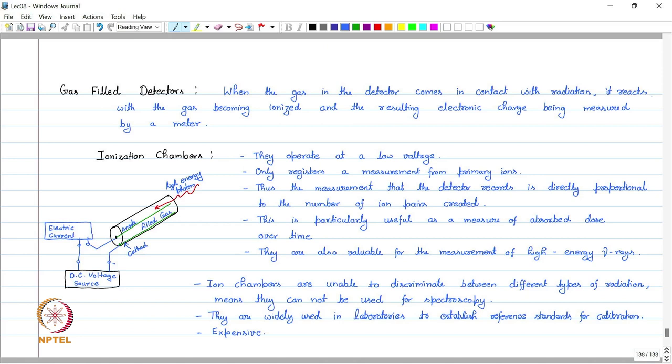So here, these ion chambers are not able to discriminate between different kinds of radiation. As we say, it cannot differentiate whether the ionization is happening because of X-rays or because of gamma rays. So if it cannot discriminate between different types of radiation, we cannot use it for spectroscopy. Spectroscopy is where we detect what kind of radiations are coming in.